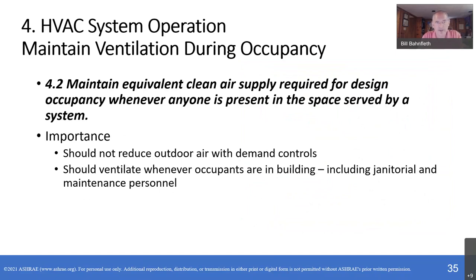We also have a number of recommendations that we've grouped under the heading of system operation. So with respect to operation of ventilation systems, maintain the equivalent clean air supply required at design whenever anyone's present. The importance of this is that it implicitly is saying don't use demand controlled ventilation to reduce outdoor air to save energy based on occupancy, because that increases risk. And the other is that we should ventilate whenever occupants are there, but not necessarily 24/7.